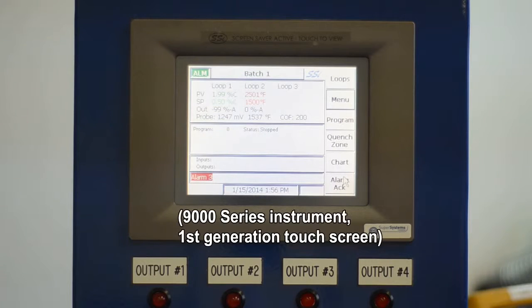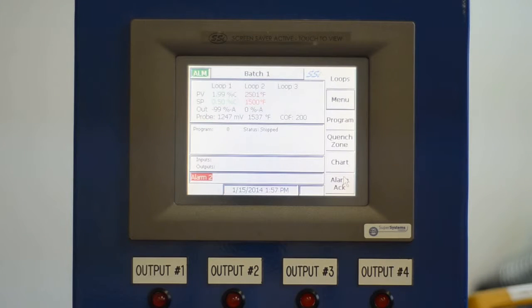So this calibration is on a first generation touchscreen for a 9000 instrument. You're going to connect up your terminals 27 and 28 with copper wire to your sourcing meter, and then we're going to go into the menu here to get to the calibration.